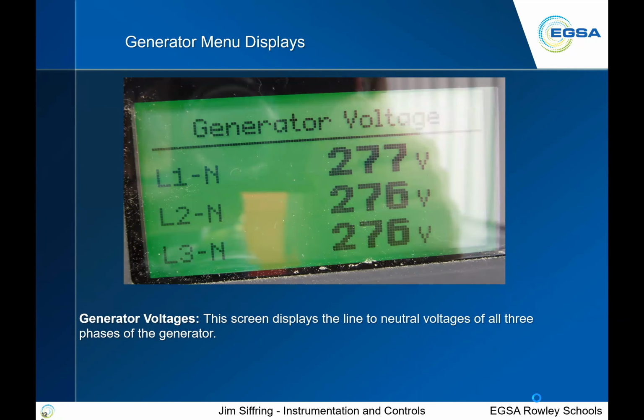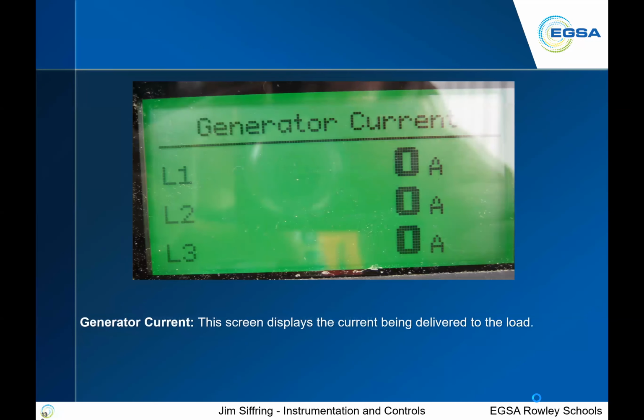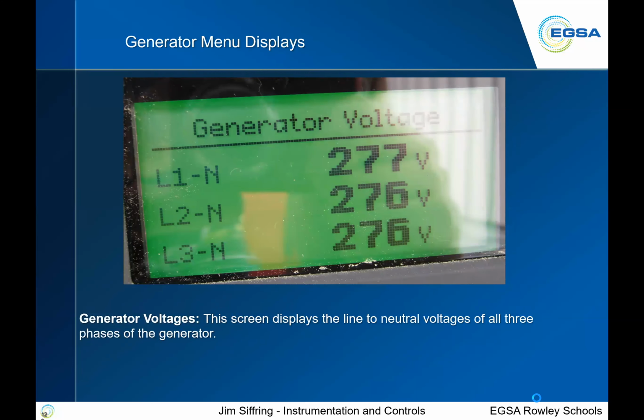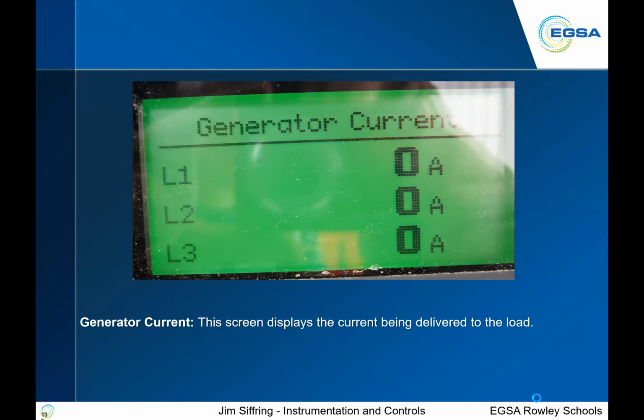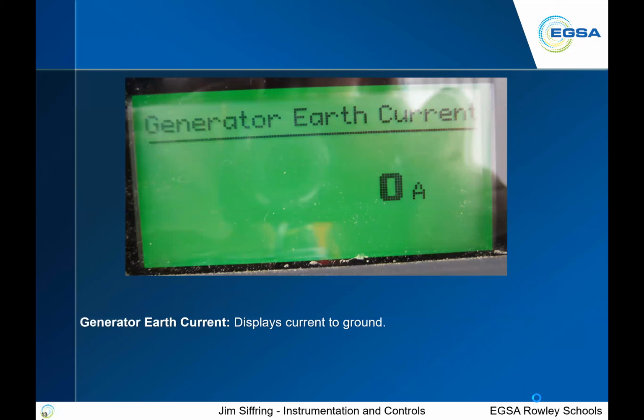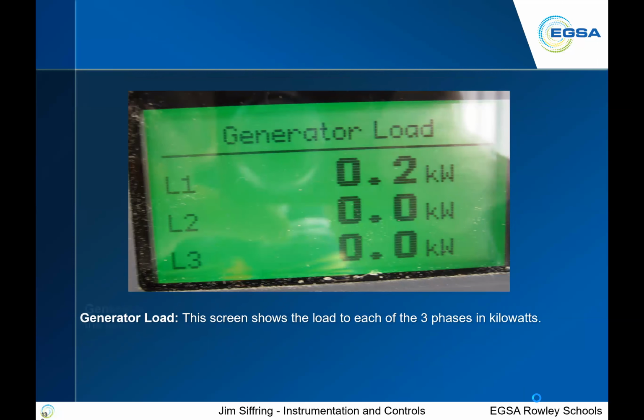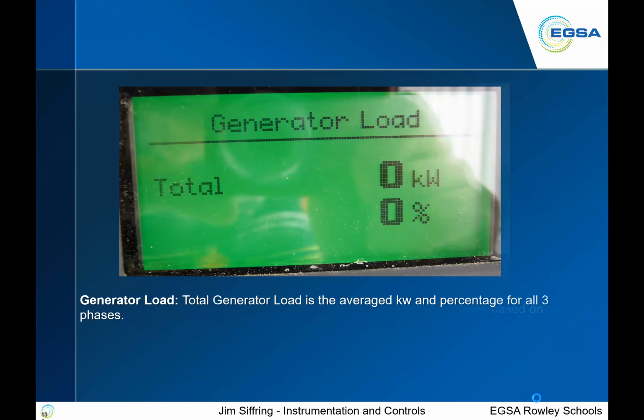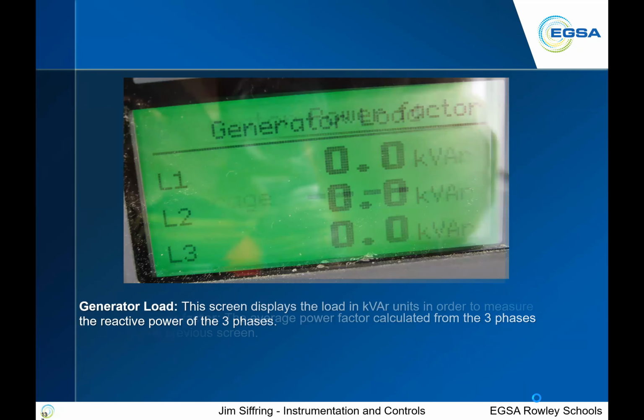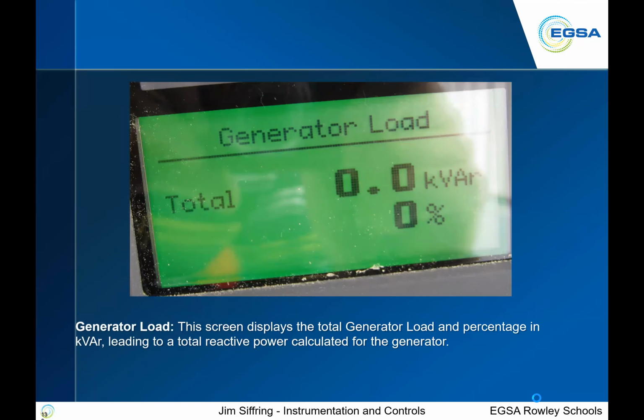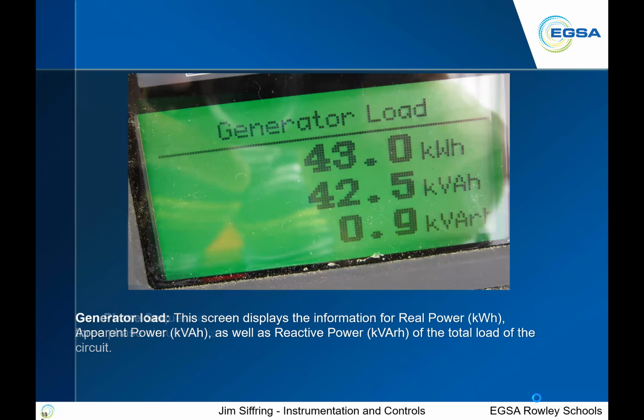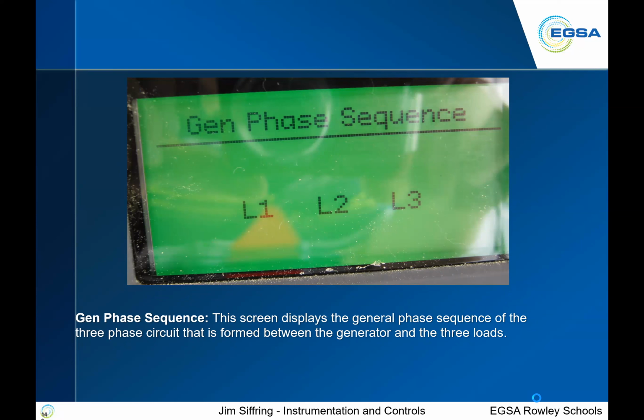Then we get in. We haven't even started on the power output stuff. So now we're into generator voltage. L1 to neutral, L2 and L3 to neutral. Remember how we talked in NFPA 110, we could switch between the three different things if we needed to see voltage, and we can see them all three simultaneously. We can also see current, all three simultaneously. Earth current, ground current. How much load do we have on the genset? Obviously not much load right now when we were running it, but kW load, percentage, power factor, average generator load, and kVAR, kVAR percentage, all these different things here. Okay, now we don't need that rotation meter right now because now we know we got ABC rotation.